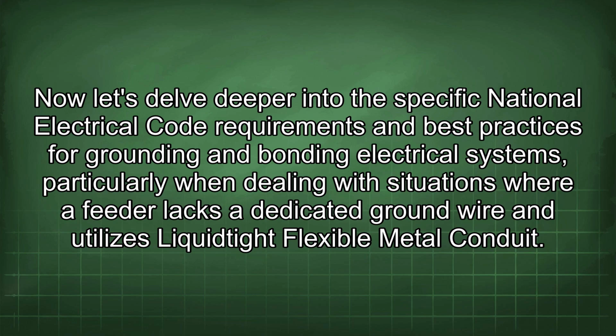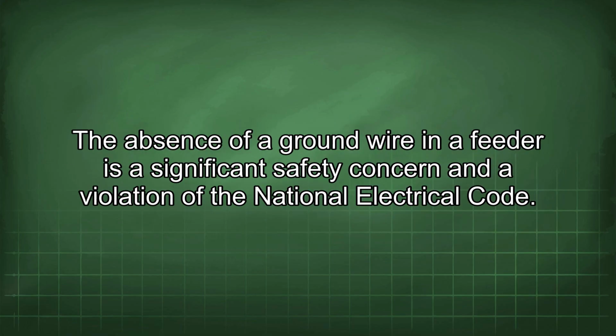Now let's delve deeper into the specific National Electrical Code requirements and best practices for grounding and bonding electrical systems, particularly when dealing with situations where a feeder lacks a dedicated ground wire and utilizes Liquidtight Flexible Metal Conduit. The absence of a ground wire in a feeder is a significant safety concern and a violation of the National Electrical Code.